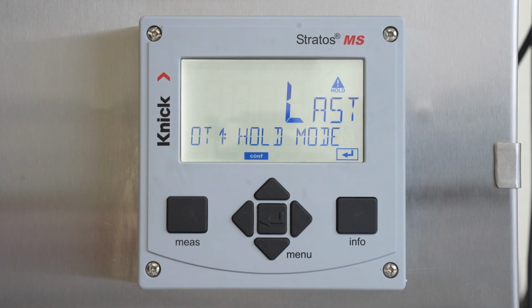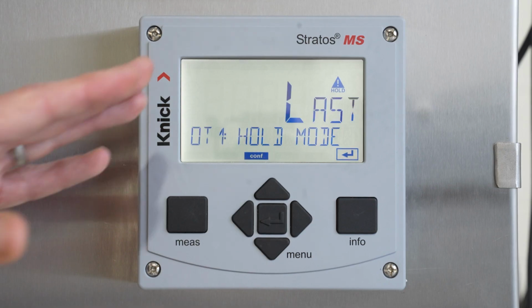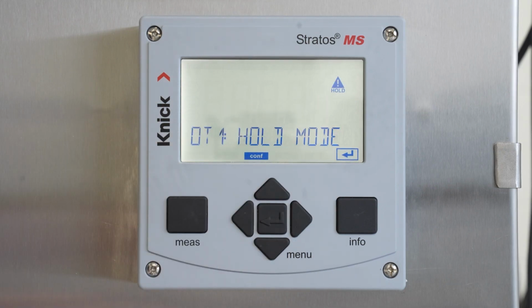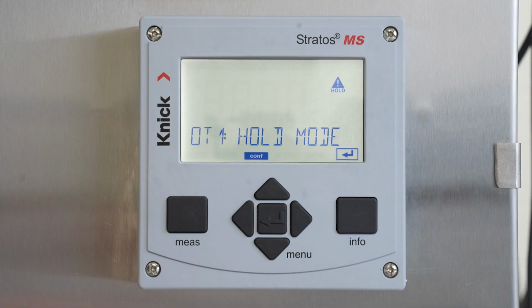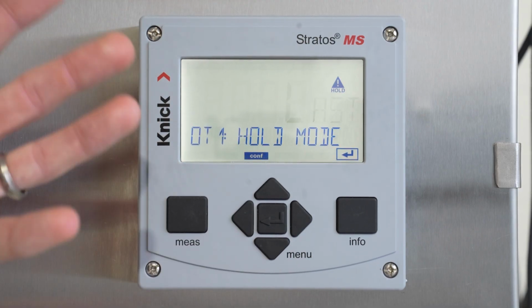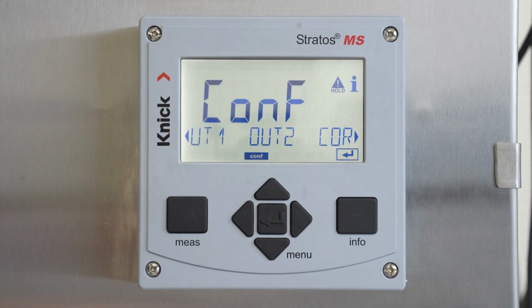Rounding out our setup and configuration of our output 1 is our hold mode. This feature allows us to select what we want the transmitter to do anytime it is in a hold state. As you can see, we can select the last usable value, or we have the option to select a fixed milliamp value. We will configure it to the last usable value and press enter. This rounds out the setup and configuration of output 1. Moving further, we could set up output 2 for a parameter such as temperature.